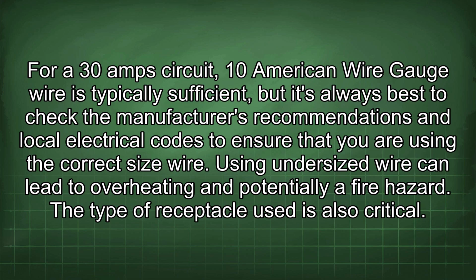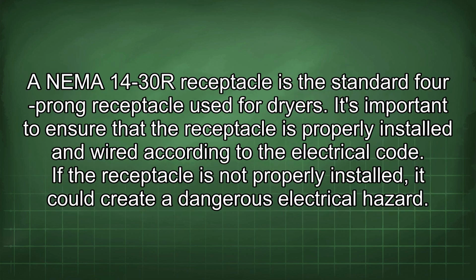For a 30 amp circuit, 10 American wire gauge wire is typically sufficient, but it's always best to check the manufacturer's recommendations and local electrical codes to ensure that you are using the correct size wire. Using undersized wire can lead to overheating and potentially a fire hazard. The type of receptacle used is also critical. A NEMA 14-30R receptacle is the standard 4-prong receptacle used for dryers. It's important to ensure that the receptacle is properly installed and wired according to the electrical code. If the receptacle is not properly installed, it could create a dangerous electrical hazard.